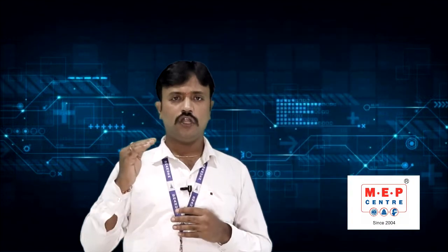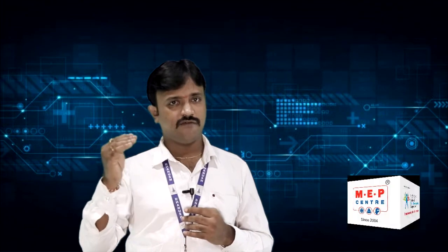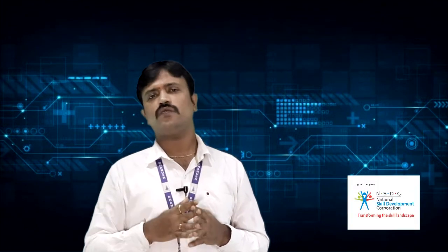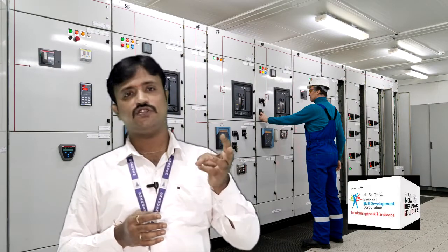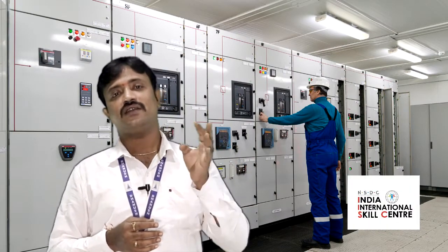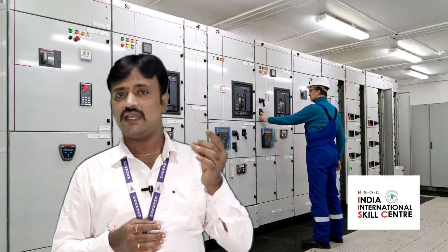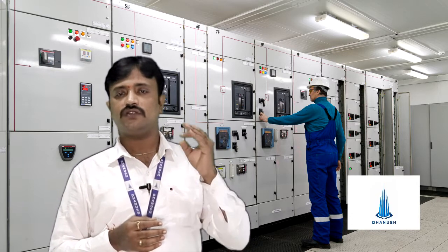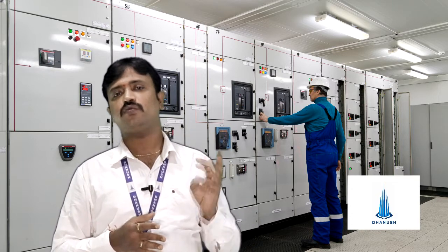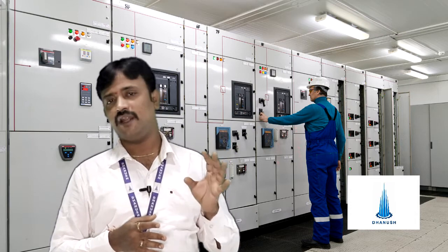Now, adding up all the flat loads, we'll get the floor loads. Now, once you get the floor loads, we'll get the MDB load, main distribution board load. So, what is DB? DB is for the individual flat, SMDB is for the sub main distribution board. It is for the floors, and MDB is for the building. So, generally, for any type of building, we'll have three things: DB, SMDB, and MDB.